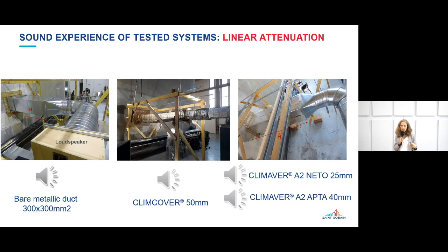Okay, now what we did is we added some CLIMCOVER. So CLIMCOVER is an external insulation material that we put outside of the duct, and we put 5 centimeters, 50 millimeters of CLIMCOVER. So I will let you hear. Okay, I don't know if you heard any difference, but we didn't measure any, because as it deals with linear attenuation, with sound absorption, as the insulation material is outside of the duct, in fact, the noise is rebounding on the metallic duct within the duct, and it doesn't reach the insulation layer. So that's why there were no differences.